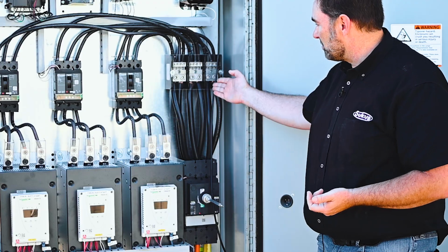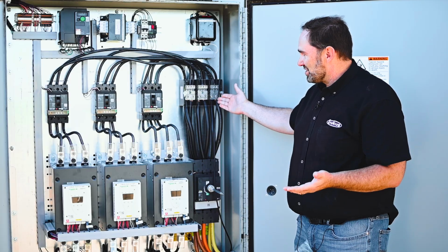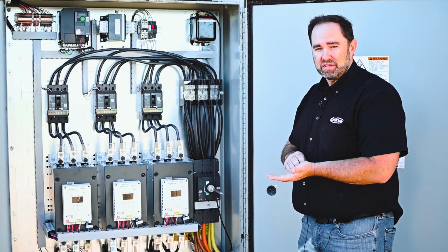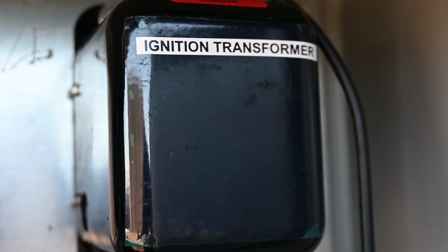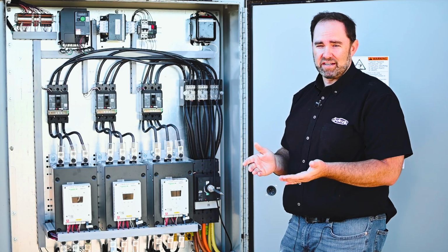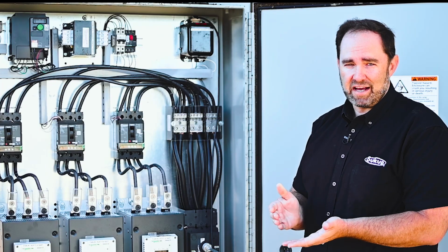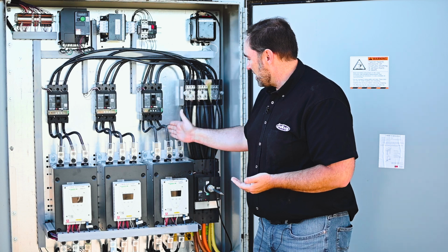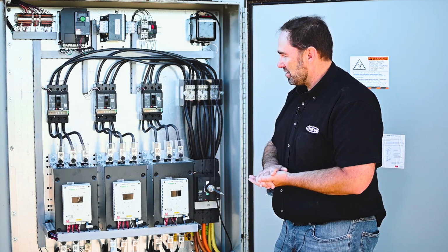From the main switch, we'll come up to a power distribution block. It does just that. It distributes power to all the different motors and components of the dryer. Up on the top here is an ignition transformer. That is simply spark ignition to give power to the spark plug or the igniter when we go to light the burner.